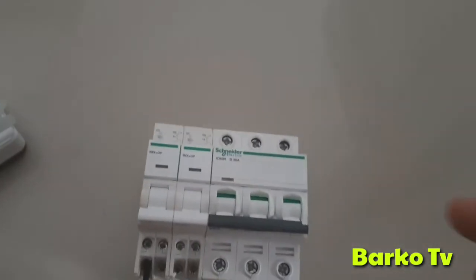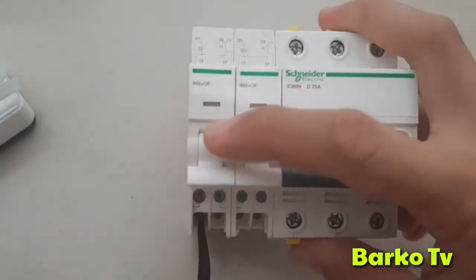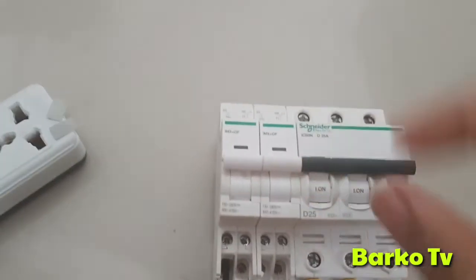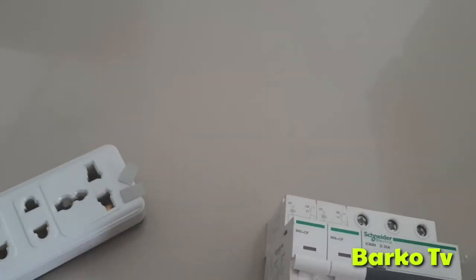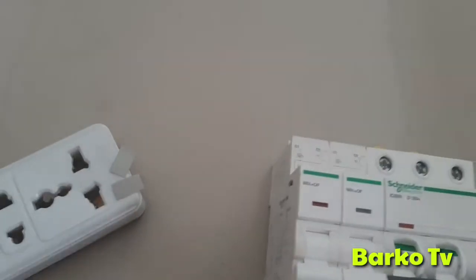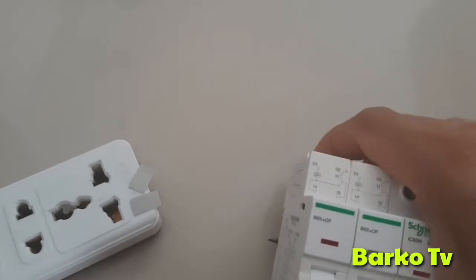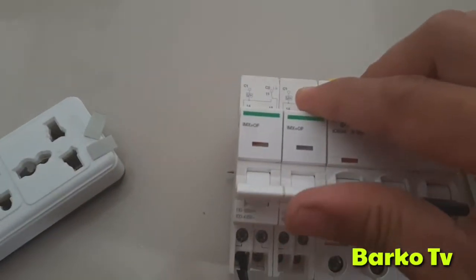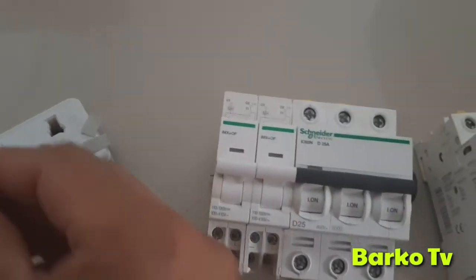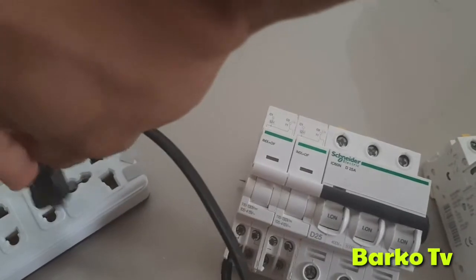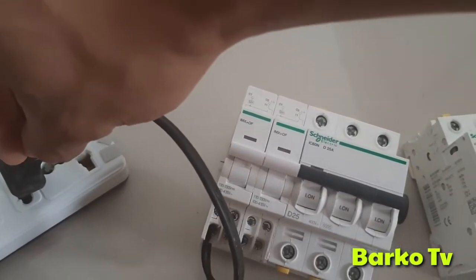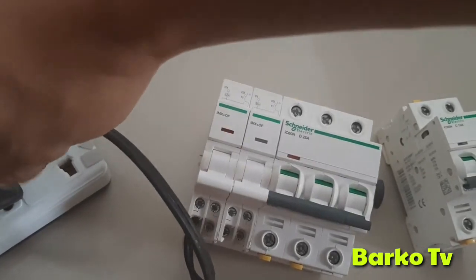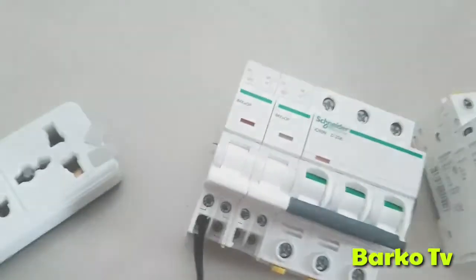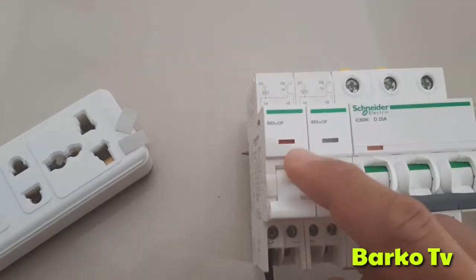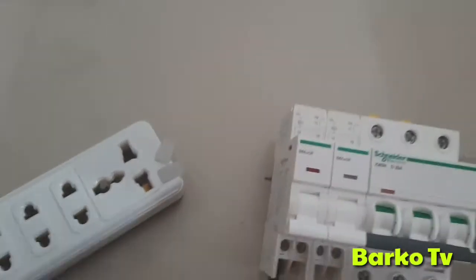In other designs that I saw, it has two shunt trips connected, depending upon the usage. Means the one is for the ASD or the preference, and the other one is for the CO2 trips, if CO2s are activated or another location of emergency stops activates the shunt trips. But in our ship design, it's only one. It matters on the contactors that activate this device so that it won't be redundant.